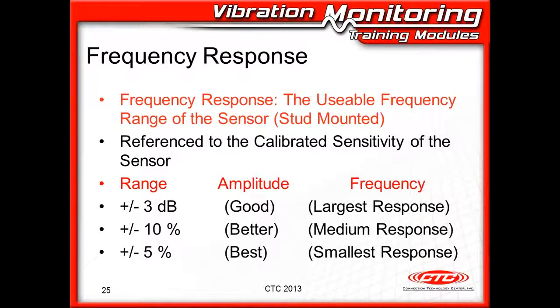When we're looking at frequency response, we're talking about the usable frequency range of the sensor when it is stud mounted. So the frequency response that's in the specifications is related to the sensor being stud mounted on one of the shakers. And the frequency response is always referenced to the actual calibrated sensitivity. So if your sensor is calibrated and it says it's 95 millivolts per G, then the frequency response will be referenced to that 95 millivolts per G.